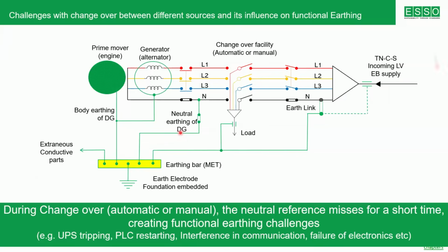In order to avoid this challenge during the changeover, the UPS manufacturer will tell you, I need a dedicated earth electrode. Connect my neutral to a separate earth electrode. So, as a result, what will happen is, to avoid one problem, you are making a compromise in the safety, and you are making a non-standard electrical installation by separate earth electrode, and this is going to create accidents and fire in future. You have one problem which is a small problem during the changeover from mains to DG or from DG to the mains.